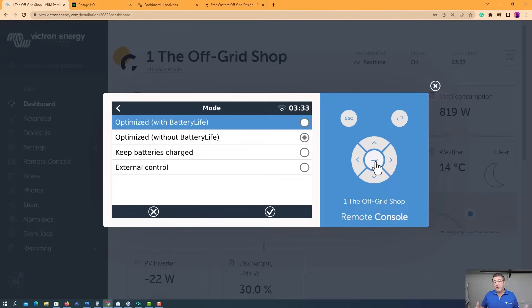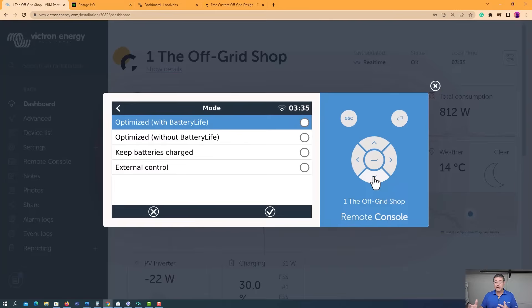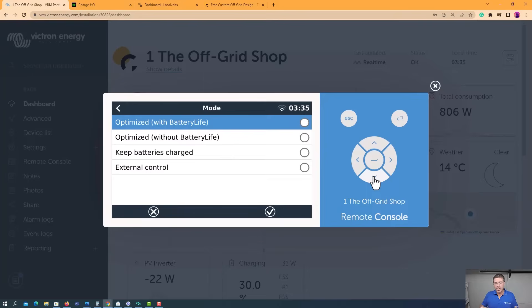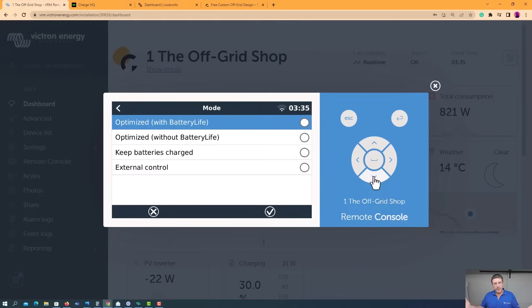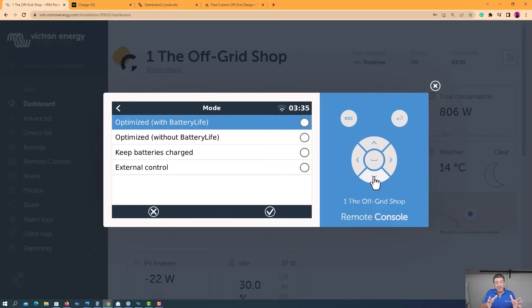When we're designing and installing a system, when there's the grid available for a hybrid system, most people are doing it for financial return. So you want to get the most out of your batteries. Drain them down as much as you can. That's what optimize without battery life will do. It'll allow your system to use 100% of the battery and then go back to the grid. Now optimize with battery life, how the optimize with battery life works. Think about it like this. It doesn't want to let your batteries operate down the bottom part of your battery. It'll take a few days for this to work out because it predicts your energy usage, how you use energy. If you're someone like me, my energy is all over the place. It really gives this setting a hard time.